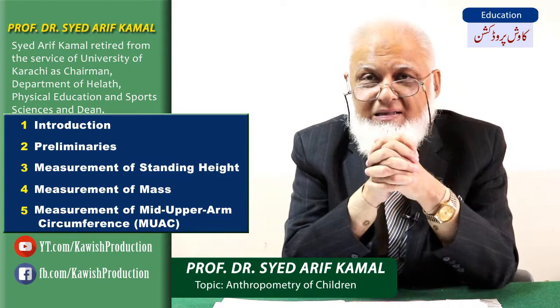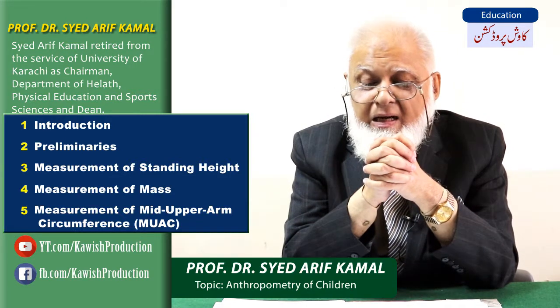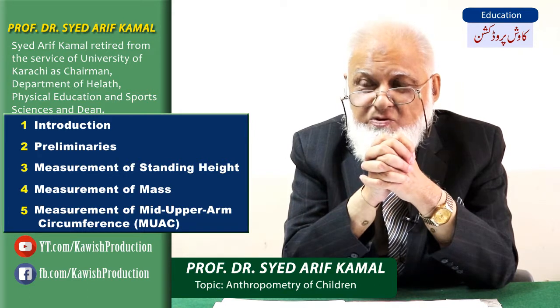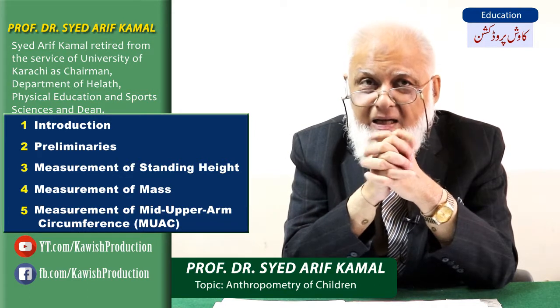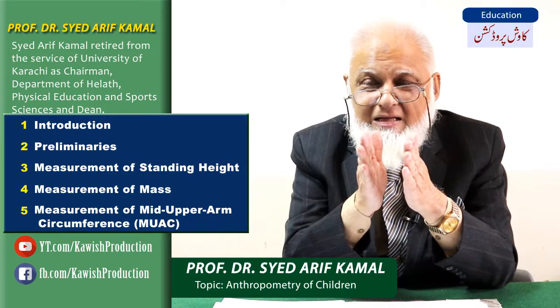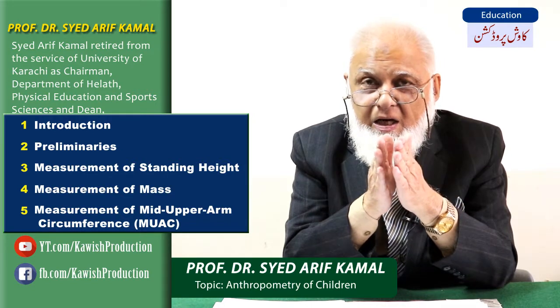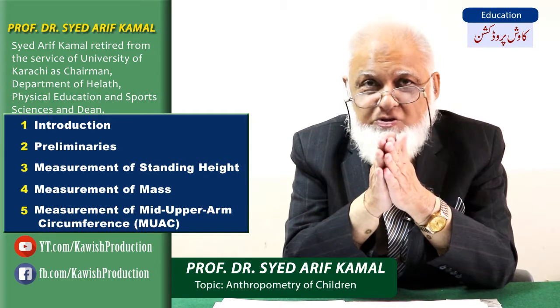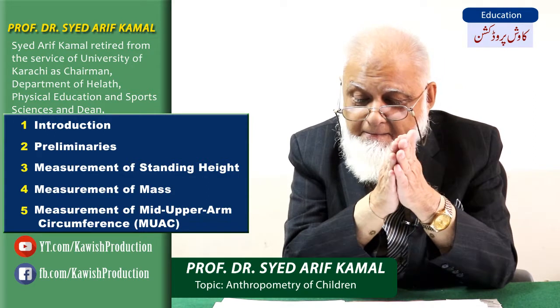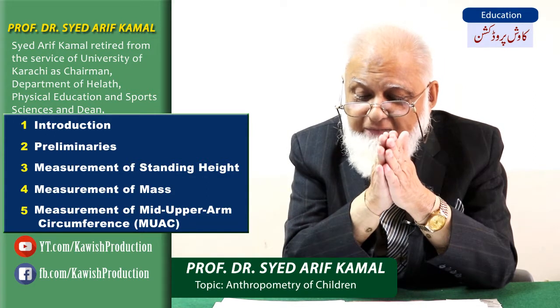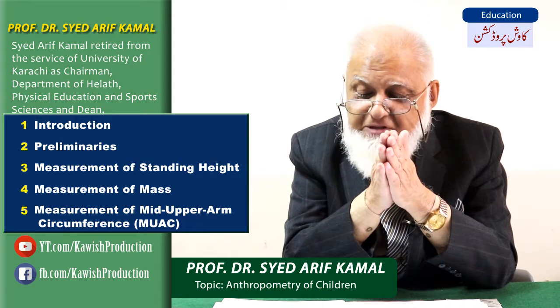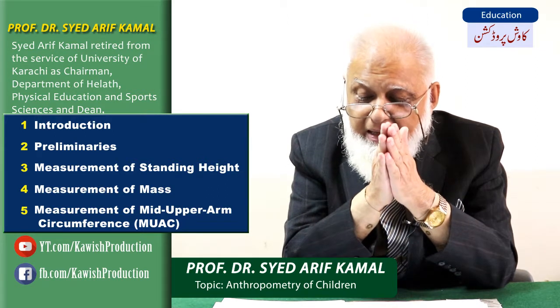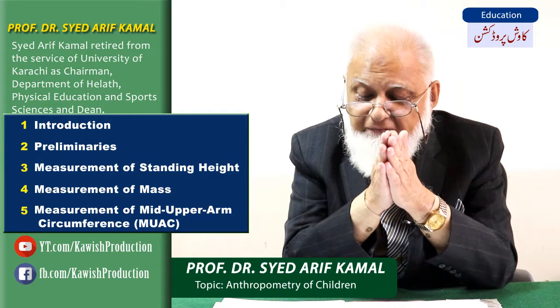When I was in Aga Khan, we had a carpeted room, and in that room we mounted that. The carpet gets pressed, and if it is pressed unevenly, that would introduce some error.